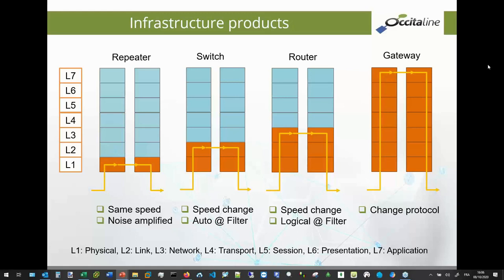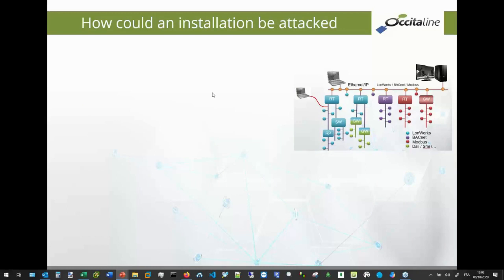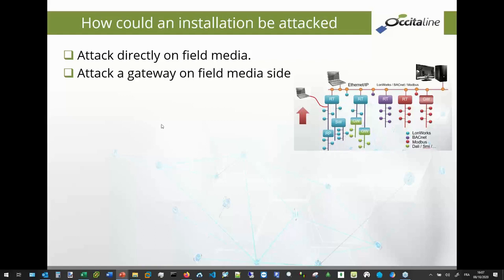And the gateway is completely different. The gateway changes the protocol, and in this case, you lose the advantage of each protocol. For infrastructure products, configuration is not needed for a repeater or a switch. For the router, you just need to configure the router. For the gateway, we need to reprogram the two sides, protocol A and protocol B, and the gateway needs to convert. When you have a conversion, you lose the advantage of each protocol.